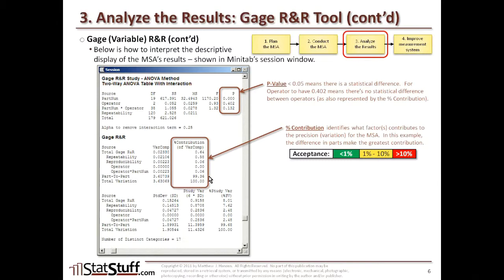We might have done multiple trials where the same part was used by each operator, which allowed us to use the crossed method for the gauge R&R. But since different parts were provided to each one, that's where we're seeing all the variation — the type of variation we'd expect to see from part to part. So this would be acceptable.